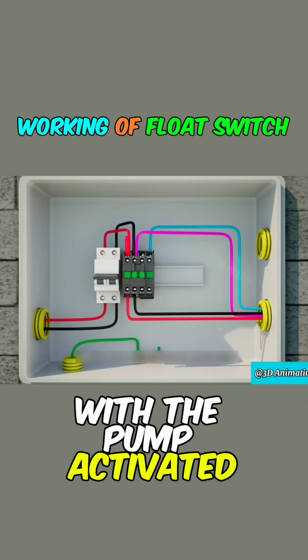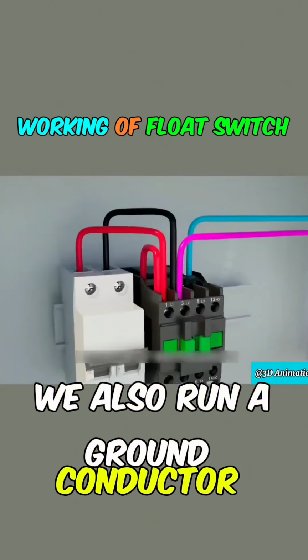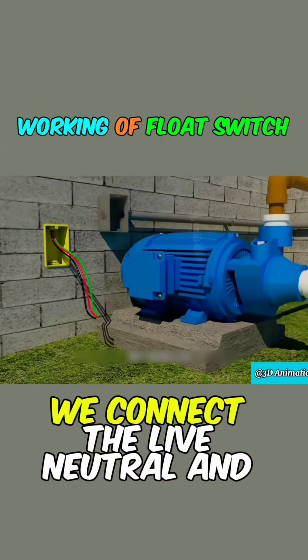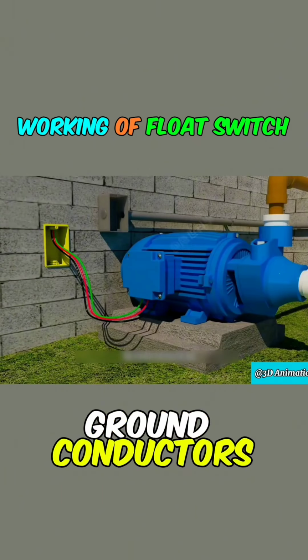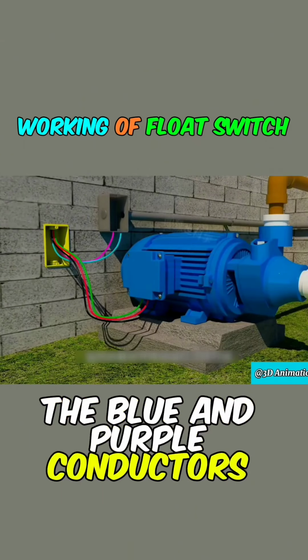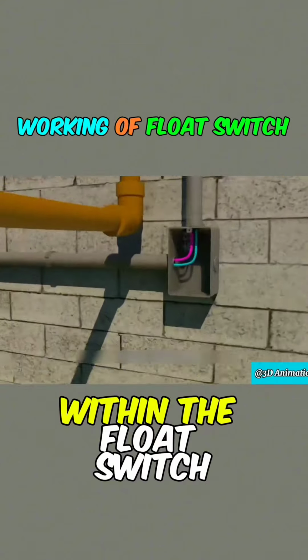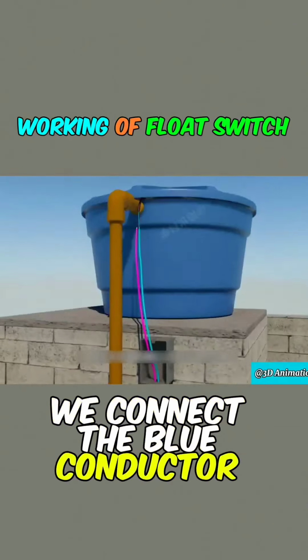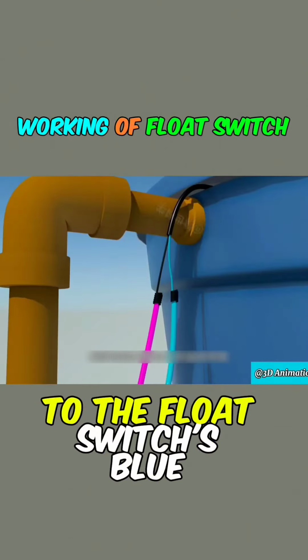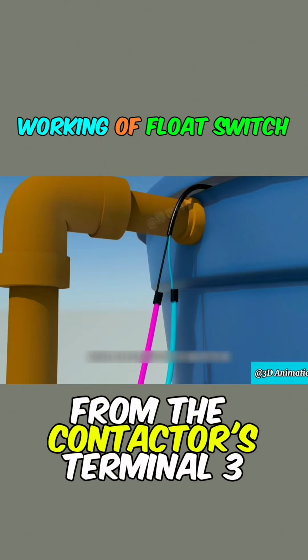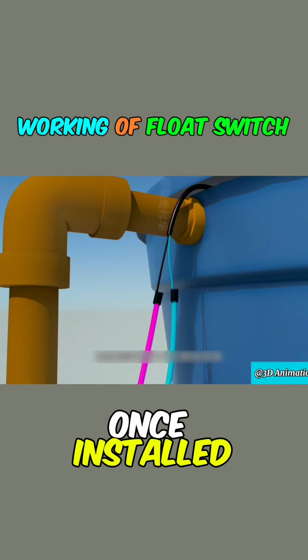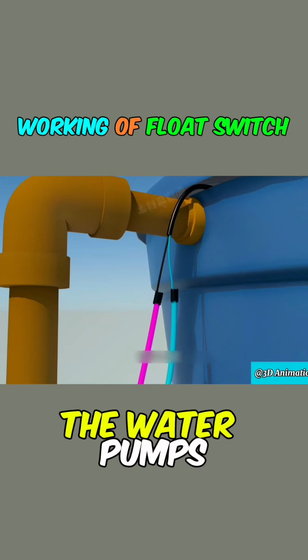With the pump activated, we also run a ground conductor to the pump. On the pump, we connect the live, neutral, and ground conductors. The blue and purple conductors lead to the float switch. Within the float switch, we connect the blue conductor from the contactor's AR to the float switch's blue conductor, and the purple conductor from the contactor's terminal 3 to the float switch's black conductor. Once installed, the float switch will regulate the water pump's operation based on the water level.